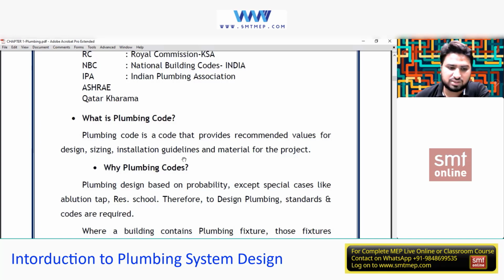It gives guidelines for installation, how things are to be installed, and the material for the project. For example, if dealing with a project near the seashore, and if I'm using GI, it won't suggest that. It will say no, don't go with GI, because the humidity ratio is very high there, because near the seashore humidity is very high.